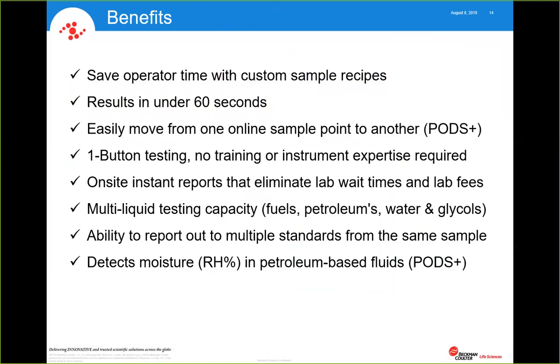And with the new PODS Plus, we actually have moisture detection capability that's reported out in relative humidity percent. So that's a new feature for that particular instrument. And it's only true for your oil-based fluids and your fuels. If you run water-based fluid like a glycol or even water through it with a moisture detector, you're going to saturate it. So it's really designed for the industrial fluids and/or the fuel oils, diesel, jet fuel, etc.